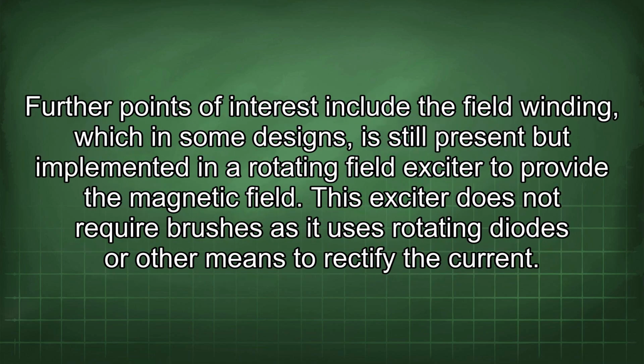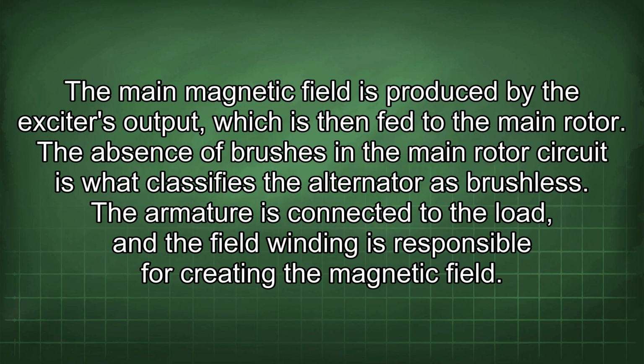Further points of interest include the field winding, which in some designs is still present but implemented in a rotating field exciter to provide the magnetic field. This exciter does not require brushes as it uses rotating diodes or other means to rectify the current. The main magnetic field is produced by the exciter's output, which is then fed to the main rotor. The absence of brushes in the main rotor circuit is what classifies the alternator as brushless.